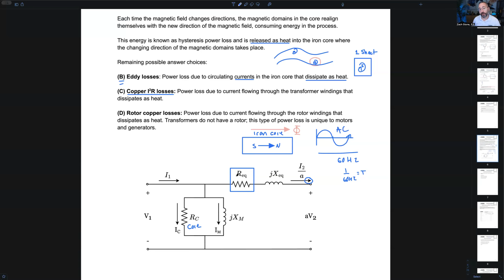As I2 over A, this current flows through the total winding resistance, that's our copper I squared R losses. This resistor in the circuit represents what we think of when we think of transformers - a big winding on the primary, big winding on the secondary. REQ represents both the primary and secondary winding resistance, the copper conductors that the current flows through in that transformer.